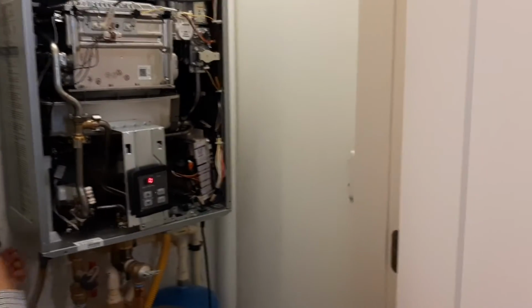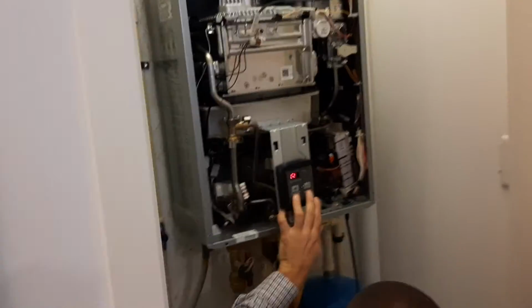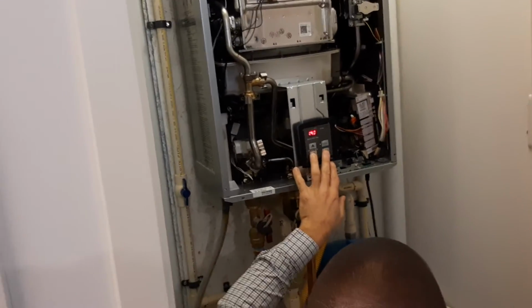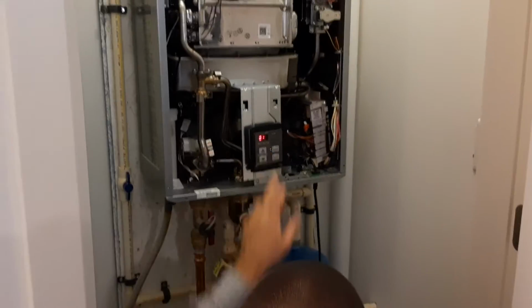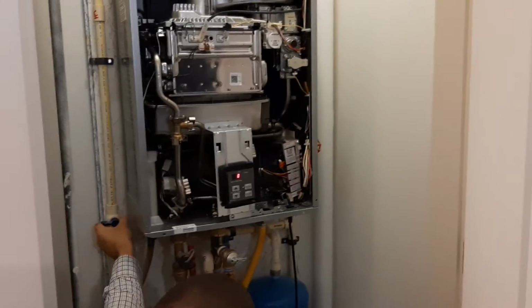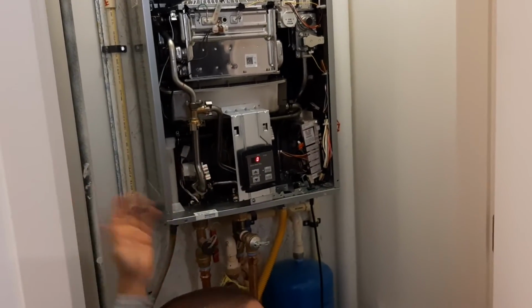But the easiest way is to pull up, walk into the unit, turn on a faucet, pull up the flow rate. If I'm at 0, shut the coil off, and if all of a sudden my flow rate goes up, I know it's leaking by.